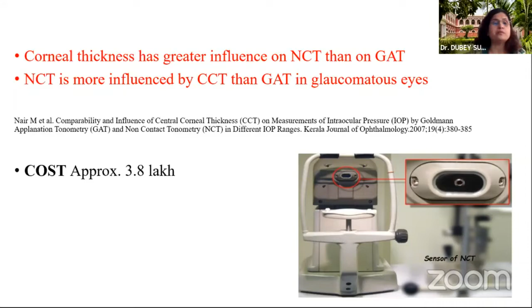And it is influenced even more in glaucomatous eyes with corneal thickness. The cost is approximately 3.8. Now the recent one is rebound tonometer. It's a contact tonometer with a very lightweight probe, and it just makes a very momentary contact with the cornea. Therefore, anesthesia is not required, and it takes 6 readings, and highest and lowest readings are discarded on its own, giving a digital display of the average IOP.